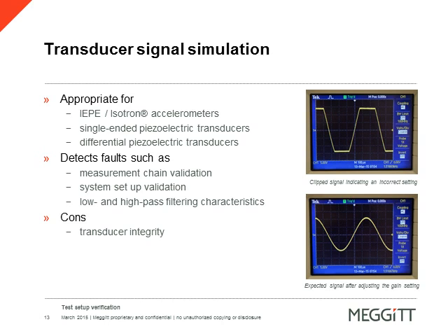Signal simulation of an IEPE device must also simulate the load associated with the constant current provided, truly simulating the IEPE transducer circuit. This is frequently done to ensure there is enough constant current to drive the high frequency signals of interest down the measurement chain. Specialized devices like the Meggitt 4830B will provide a known amplitude up to 20 kilohertz, which can many times provide out-of-band frequencies to ensure proper system low-pass filtering is enabled. This test method validates the measurement chain, the gain settings, and the filtering of the system.